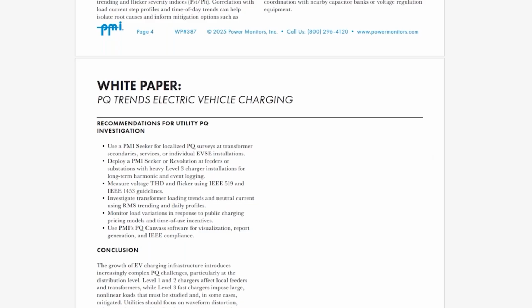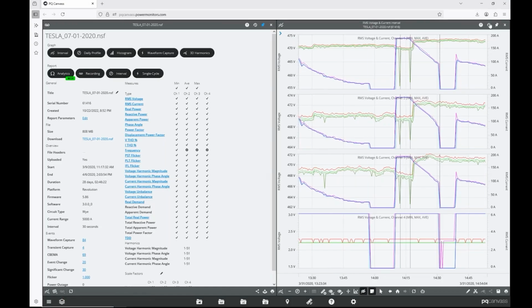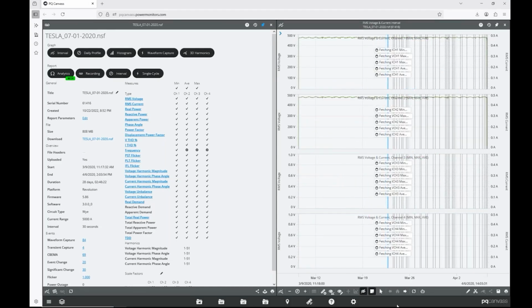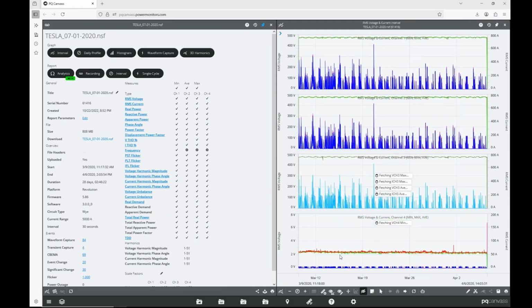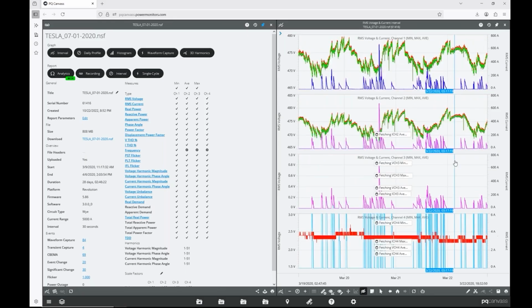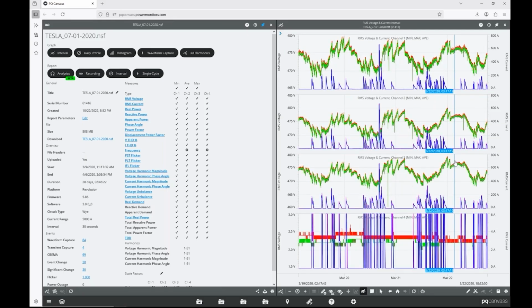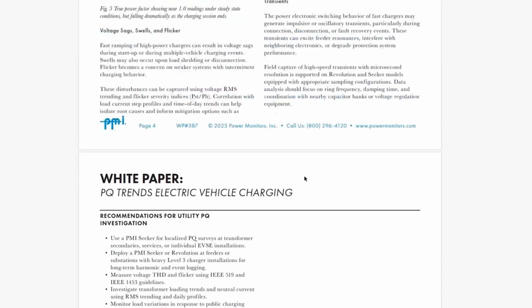For example, in this recording, there was only one day where we saw the worst case current load. So you don't want to just leave it for an hour or two or even a day. You want to leave it for a fairly large amount of time to capture the combination of all the bays being full and at maximum charge, because that doesn't happen every day in many locations. And you want to make sure you enable harmonic recording, or at least THD for voltage and current. Periodic waveform capture is useful in a flicker because you want to not miss any of these power quality issues.